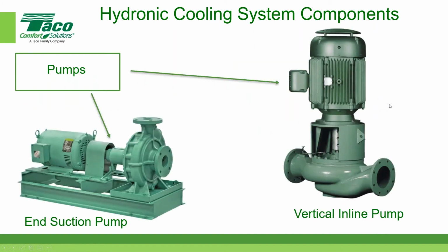So here are the two most common pumps in our industry today. The one on the left is an end suction pump, and it's base mounted. From Taco, you can get end suction pumps either base mounted or close coupled. But I've only shown the base mounted end suction pump. One of the interesting things about end suction pumps is that the water enters the pump at the end of the suction and then leaves vertically upward. There is a 90 degree angle between the suction side of the pump and the discharge side. And the suction side of an end suction pump is, generally speaking, one size larger than the discharge. So if the inlet on this pump happens to be 4 inches on the suction, perhaps the discharge is 3 inches up here. So those are the kind of characteristics.